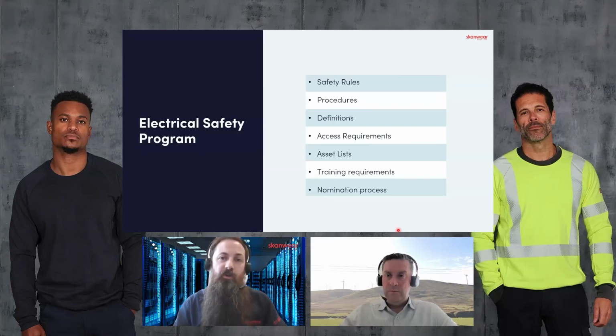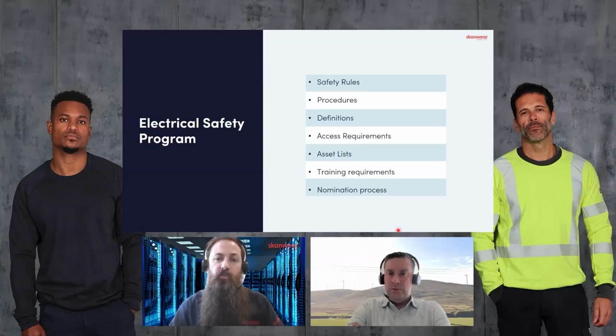So if we're going to go into one of those compartments, a key precaution might be to put those automatic tap changers into manual, so that in the event of a fault while it's changing tap position, it's not going to operate when you're in that compartment. We wouldn't know that without having the asset list. It all forms part of the electrical safety program and into your entry requirements.